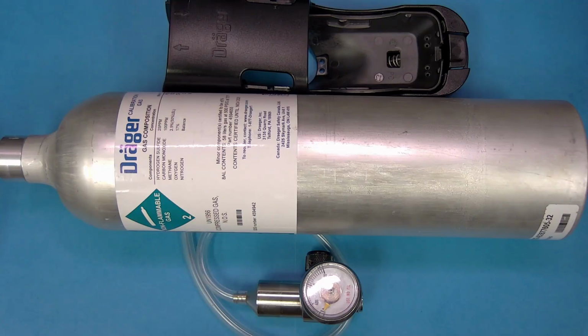Bump testing is a critical process that ensures your monitor will alarm if exposed to the gases your monitor is configured to detect. Bump testing can take place manually in a bump test station or on the X-Dock. Today, we're going to discuss the manual process. You will need everything pictured, and at the very top is the bump test calibration adapter, a cylinder of cal gas, a fixed flow 1/2 liter a minute regulator, along with a piece of tubing.